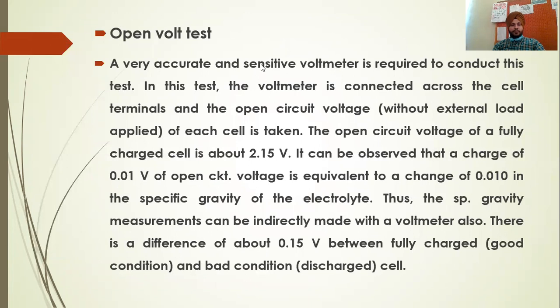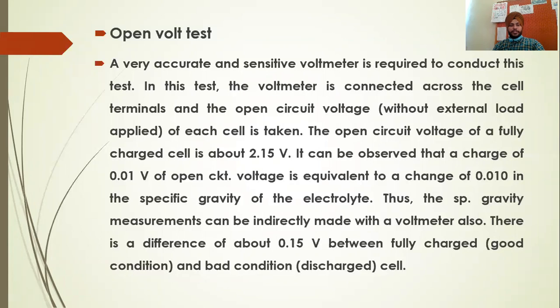Next is the open volt test. A very accurate and sensitive voltmeter is required to conduct this test. In this test, the voltmeter is connected across the cell terminals and the open circuit voltage of each cell is taken. The open circuit voltage of a fully charged cell is about 2.15 volts.